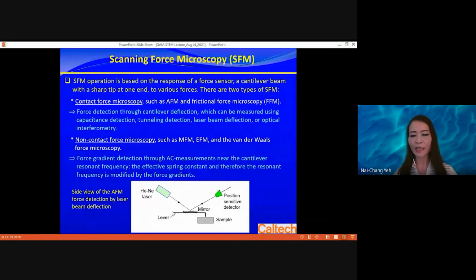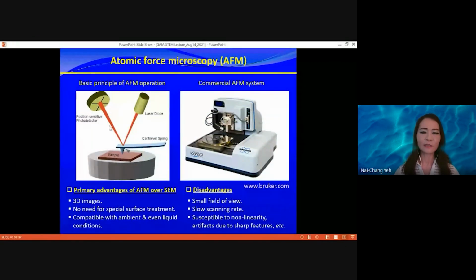So what it is, this is my cantilever, and this is a sample, a side view. When I scan this tip across the sample, if the sample has height variation, then this cantilever will move up and down. When it moves up and down, you have a mirror here, so the mirror will be moving up and down. If you have a laser focusing on the mirror, then the position of the light will be changing as you move your tip up and down. From that, you use the deflection beam position for position-sensitive detection of the light, and you know how much the cantilever has moved. This is again another three-dimensional picture to show you.